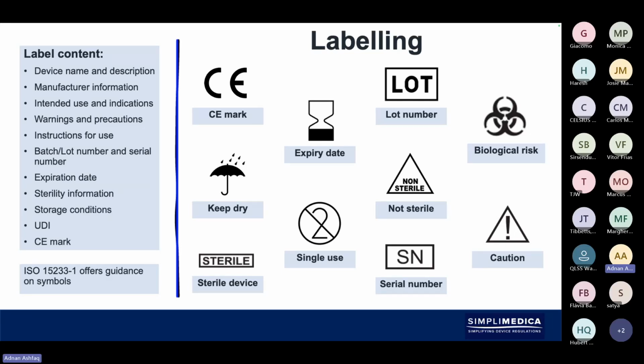There are also some other symbols that were introduced because of the MDR. Specifically, if you've got an implantable, there's an implantable card that you have to introduce, and then there is also another ETO or sterilization symbol that's been introduced as a result of the MDR.